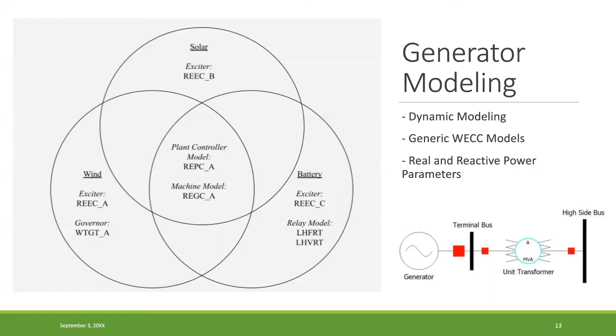We modeled our generators to have real power dispatched at a set point from a minimum to maximum, as well as for the reactive power capability. The bottom right corner of the screen shows us the manner in which we connected our generator models into a point of interconnection, where then the power goes into transmission. This typical model is where we have the generator, a terminal bus, a unit transformer, and then the high side of the bus will then follow a point of interconnection.